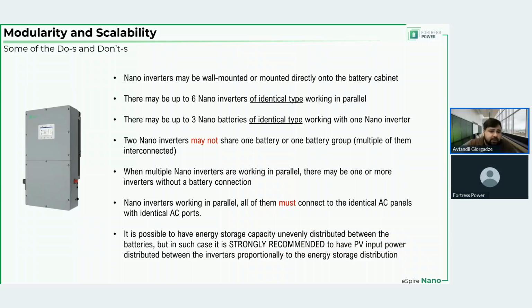Inverters working in parallel should all connect to the same AC panels with the same ports. So you cannot have a situation where you have multiple backup panels and one inverter is responsible for one and the other is responsible for another. Maybe there are batteries connected to each inverter or not. You cannot have some of the inverters with interconnection to a generator output and some of them not.